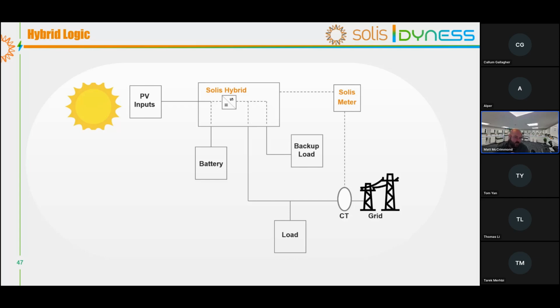Another hugely important thing to talk about is the PV and battery. So on the DC side, you can see in the middle of that diagram there, we have the inverter right in the middle, the DC side into the AC, but the DC side has a charging circuit. So what that does mean is, hypothetically, we have a 5 kilowatt PV array, and maybe, for example, a 3.6 kilowatt inverter. What is possible is that the PV can be pushing 3.68 kilowatts out of the inverter, and then also using the additional PV energy to charge the battery.